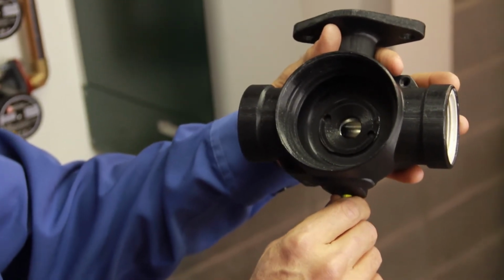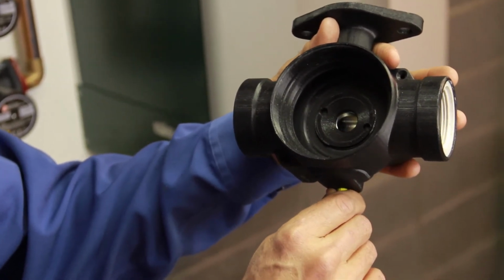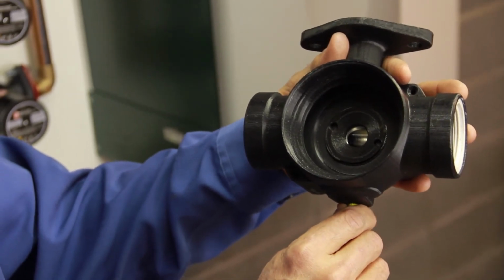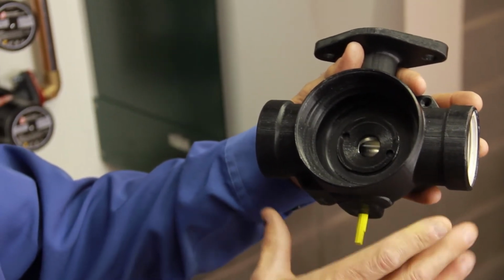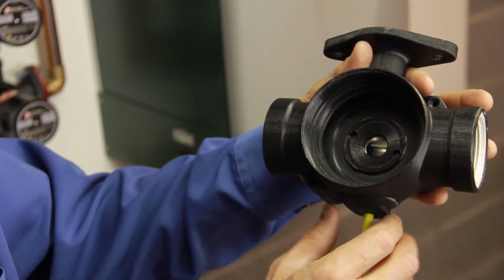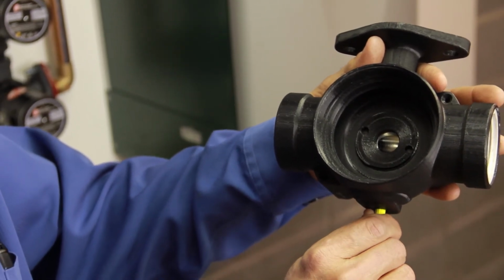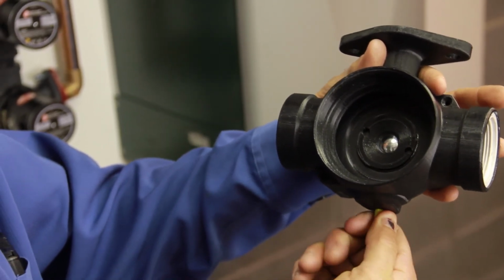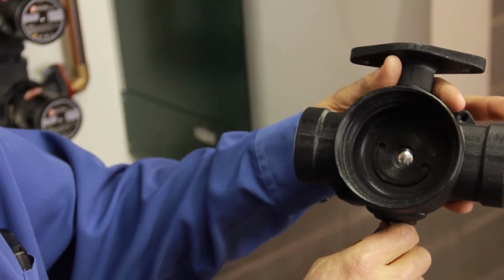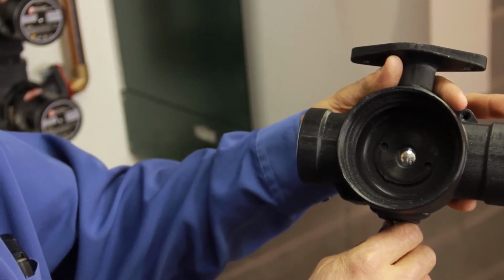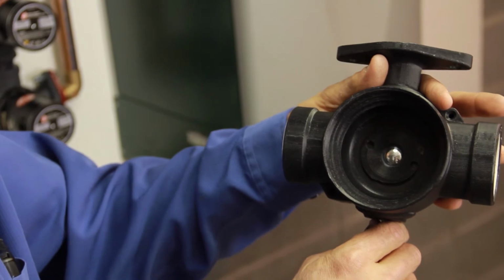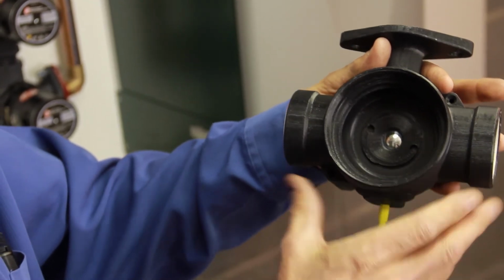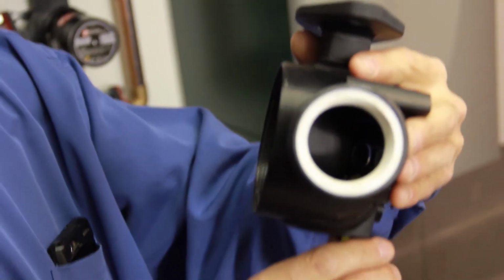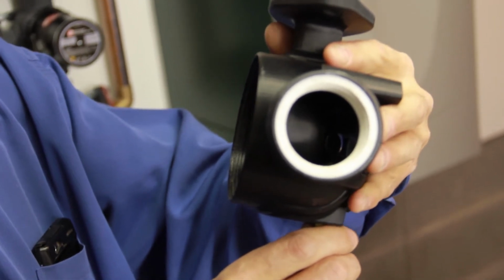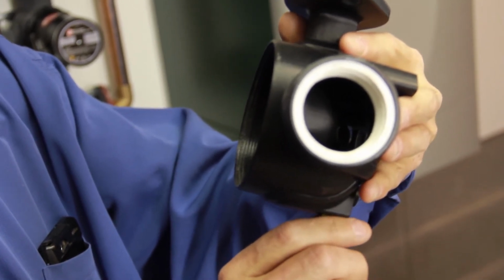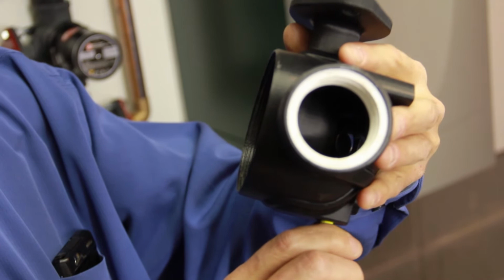In the open position, the 3 ports of the ball are exposed to the impeller, and water is free to flow from the common pipe to the impeller. In the closed position, the solid portion of the ball seals against the impeller side of the cavity, thus isolating the suction of the pump from the common body. The pressure drop through the common body is the same whether the valve is in the open or closed position.